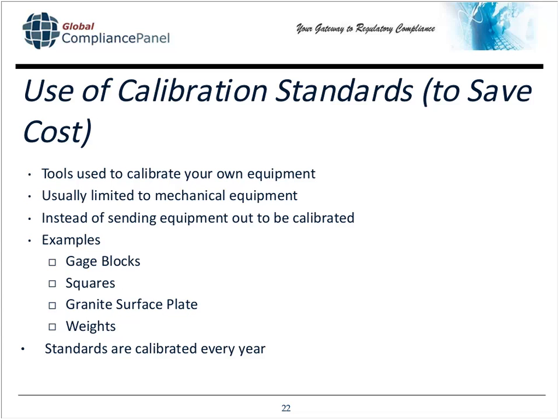Things like gauge blocks, squares, surface plates, weights. You make sure that your standards are calibrated every year. Even if you use those standards to calibrate one of your pieces of equipment that's only calibrated every other year, you definitely want to make sure that you send the standards out every 12 months.